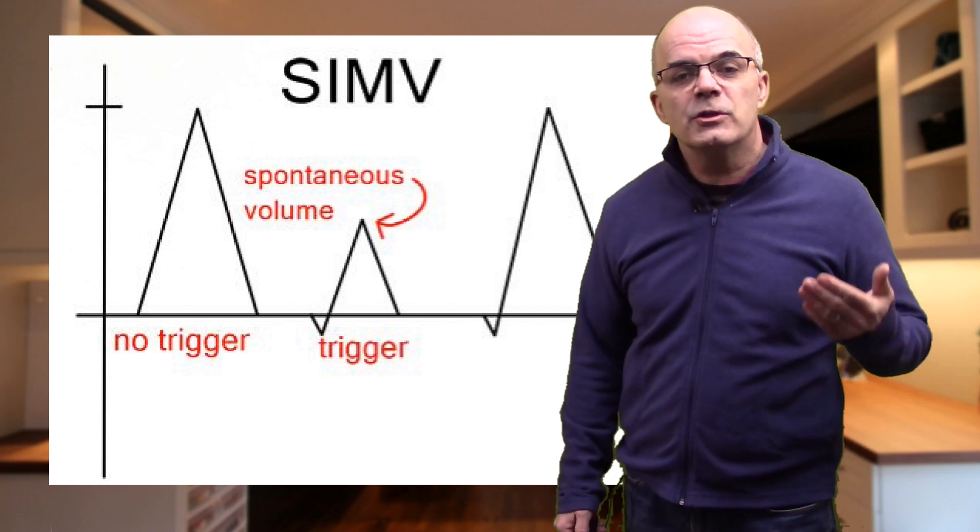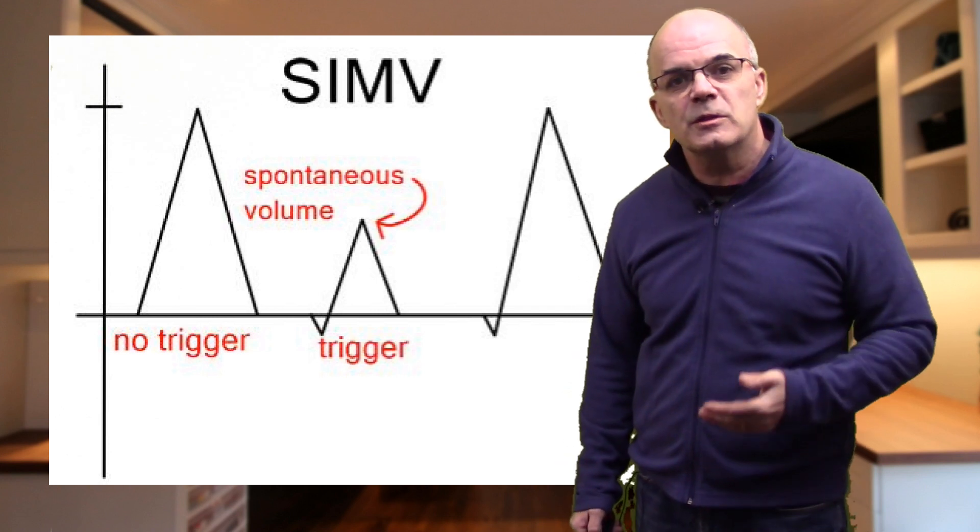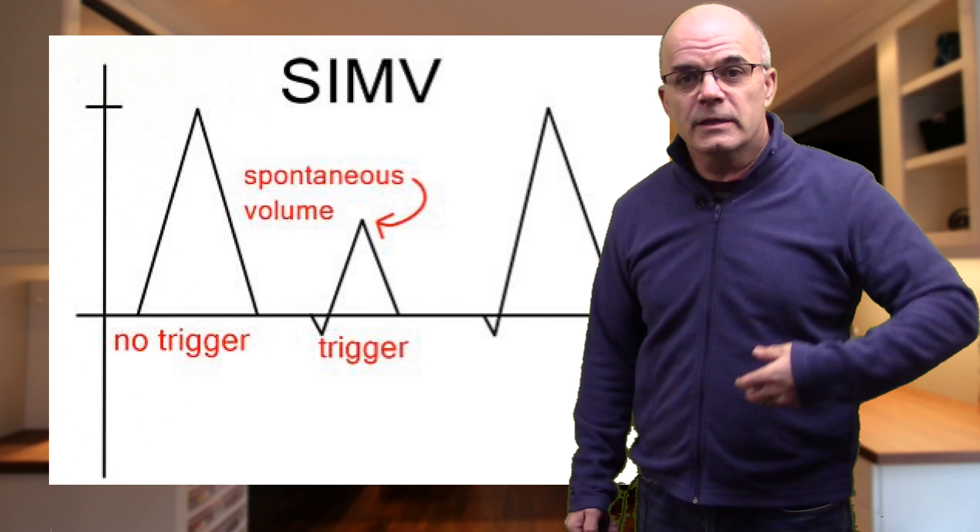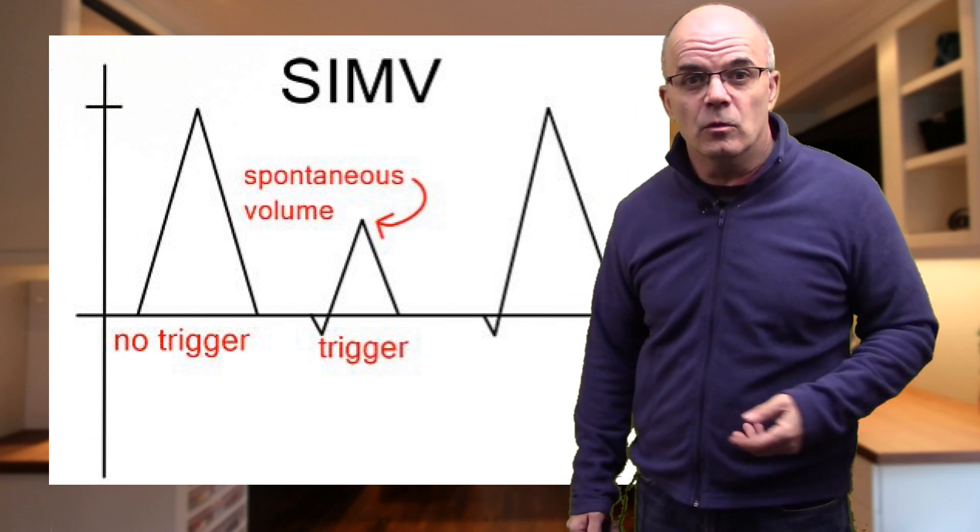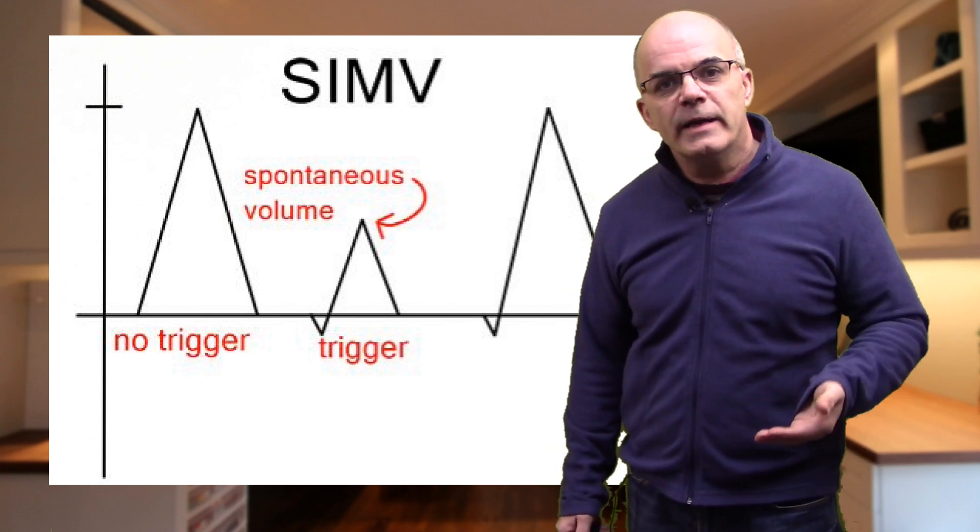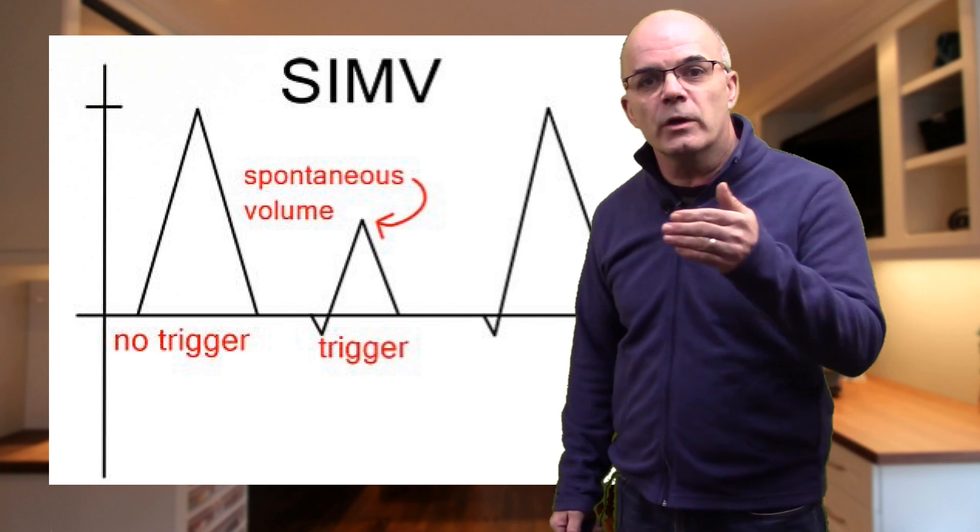This mode is more suited to the patient who needs to start doing some of the respiratory work for themselves. They're starting to use their own muscles a little more. By decreasing the mandatory rate, we can enable the patient to work a little harder.